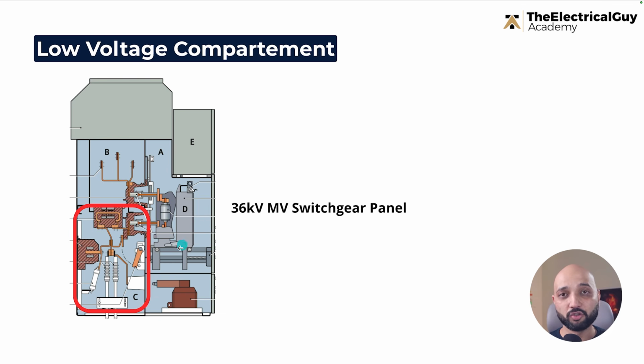There will be a circuit breaker chamber. There also 36 kV will be present for sure. And the circuit breaker will also be rated for 36 kilovolt. Then there will be a bus bar compartment that will also be rated for 36 kilovolt. But then comes a compartment which does not operate on 36 kV at all. It operates on maybe, let's say, 110 volt DC, 220 volt DC, 48 volt DC. And that compartment is what we refer to as the low voltage compartment.